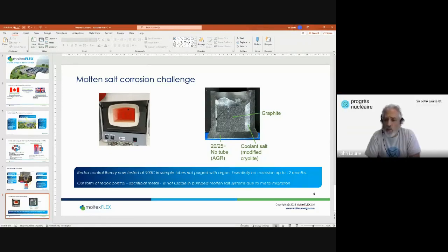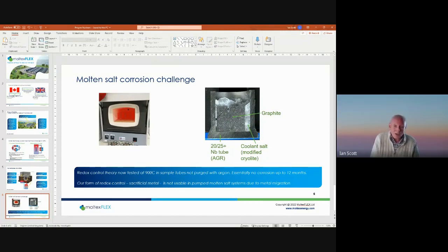Nicola Breton asks: why only 16 megawatts electric — why so small? Part of the trade-off in getting a reactor that operates entirely by natural convection is that you cannot achieve very high power density — for high power density you must pump coolant through very fast. The aim here was full passive operation, which requires relatively low power density, and therefore unless the reactor were extremely large physically, it needs to be small. Somewhat to our surprise, that size turns out to be something of an economic sweet spot in terms of manufacturability and overall cost.